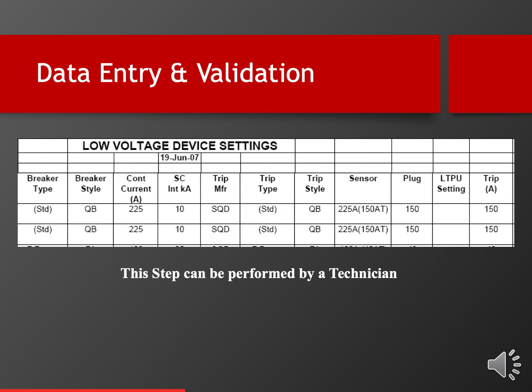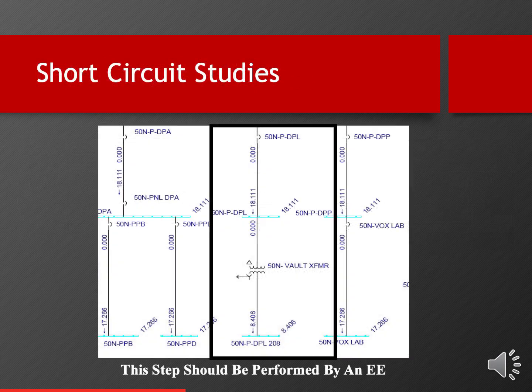Let's go to the next slide. Now what you're seeing here is the short circuit calculations on the system. And again, if you look at this, these numbers are in thousands of amperes. So like under the 50N PDPL bus, it's listed as 18.111. That would be 18,111 amperes of current flow. So this is the short circuit part of the study.